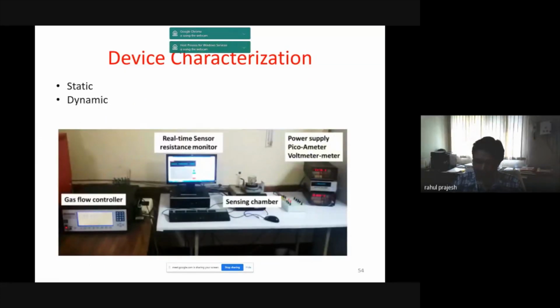Once you have characterized all the parameters, and the parameters are according to your design, and your sensor is as per the requirement, then you go for the actual measurement of the sensor. Actual measurement means you apply gas on the sensor and see the electrical response of the sensor. Now there are two methods of testing. One is static, another is dynamic. Let me tell you, basically you have a chamber where your sensor is placed. So this is your sensor.